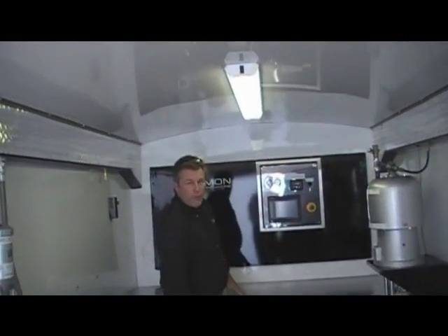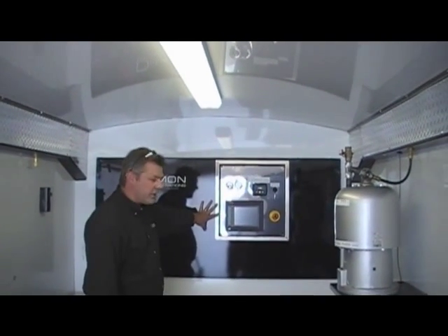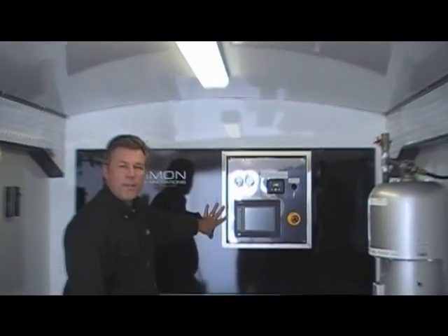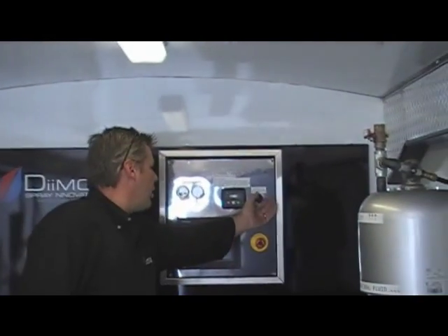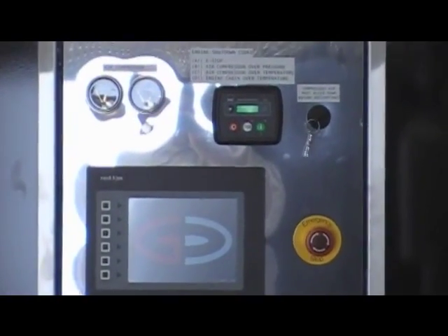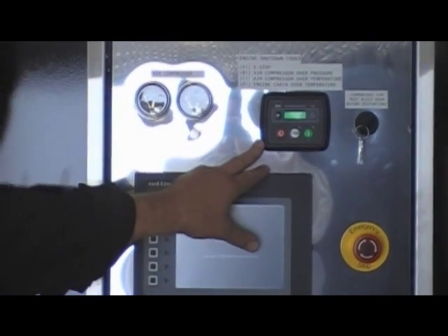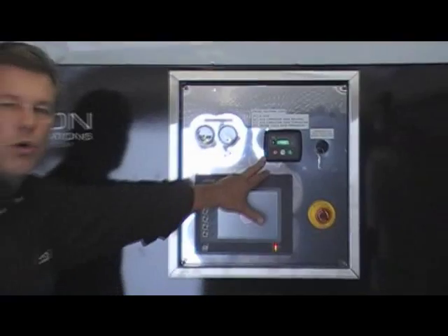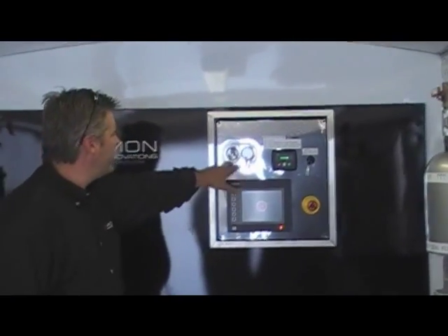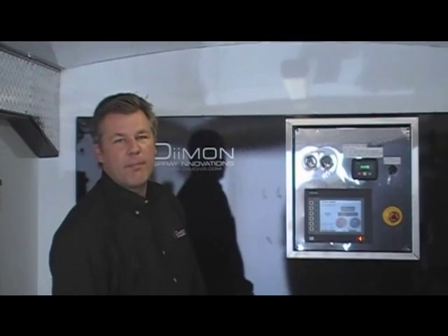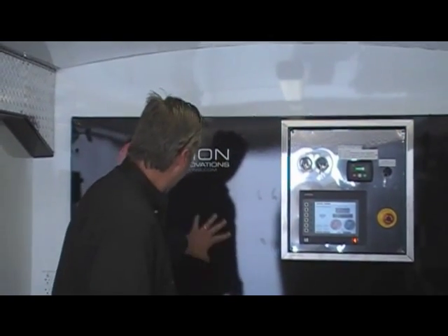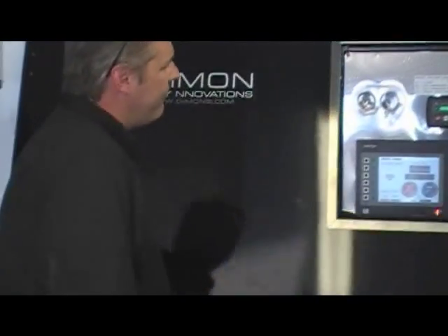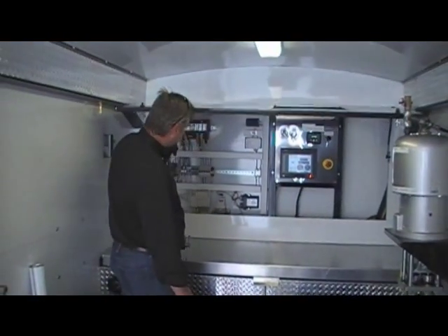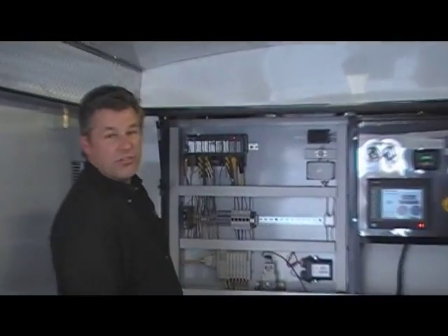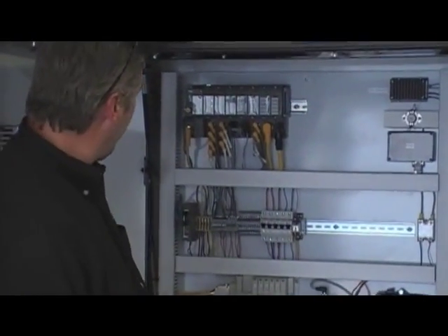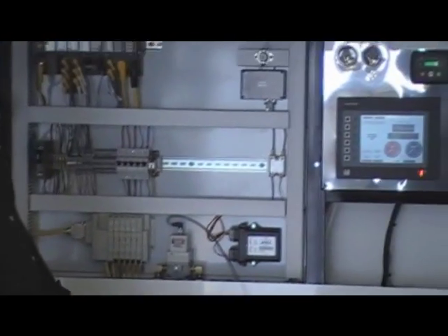Up front we have the control panel, and what this control panel does is it operates the settings for the temperatures and pressures for the rig. Simple on-off switch gets it going. This control panel here operates the motor, and it has the automatic shutoffs for the over temperature or low oil pressure, things like that. And these two gauges are for the compressor's temperature and pressure. The controls for the system are underneath this panel here. A very simple control system, basic PLC type controls, pneumatic controls, and standard breakers for easy reset if anything should trip.